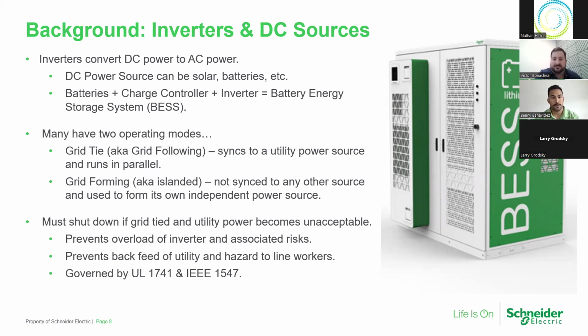Next slide, please. I'll just add that when we're talking about battery energy storage systems, these are commercial offerings, behind the meter, and it can even be front of the meter. These systems are all in one. They include the inverters, the batteries, the racks, the power control system, and the HVAC systems. They're compartmentalized and tested to UL 9540 and 9540A for thermal propagation. So commercial BESS is a little different than residential. When you specify a BESS, you're getting an all-in-one that's designed for outdoor installation.